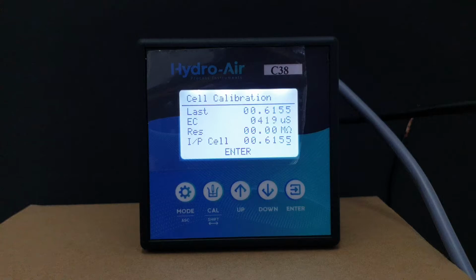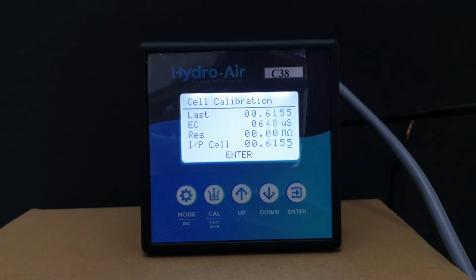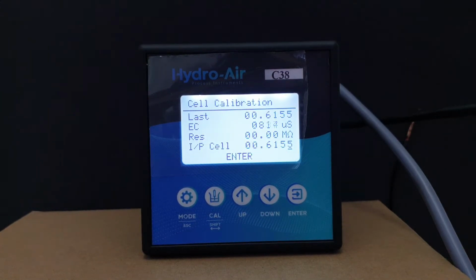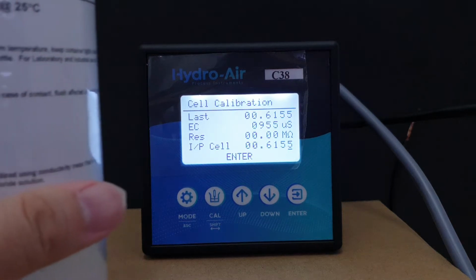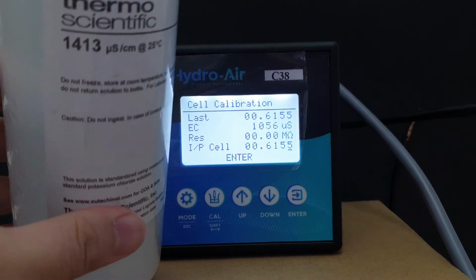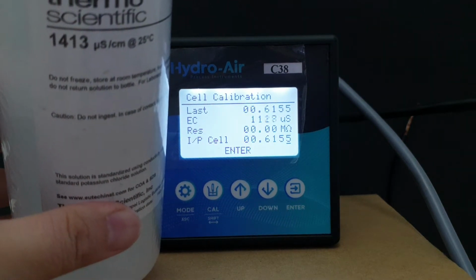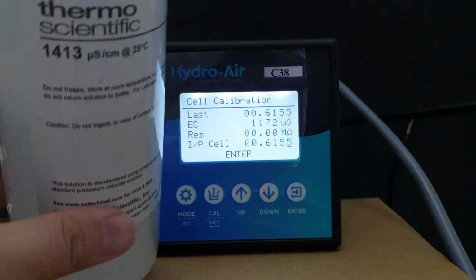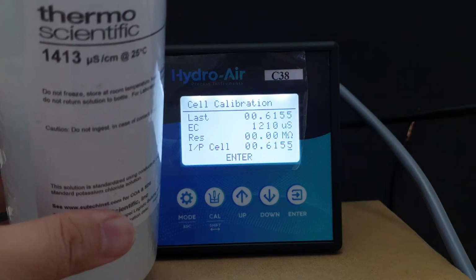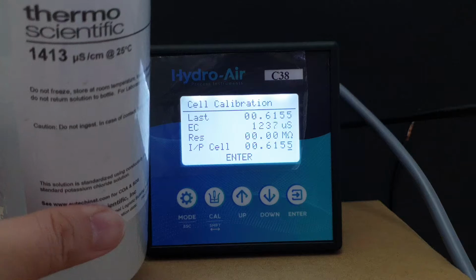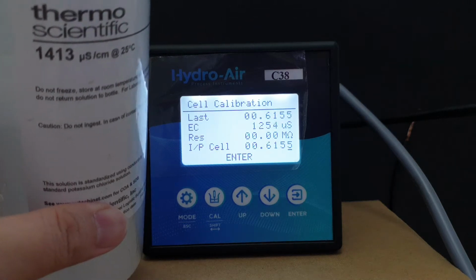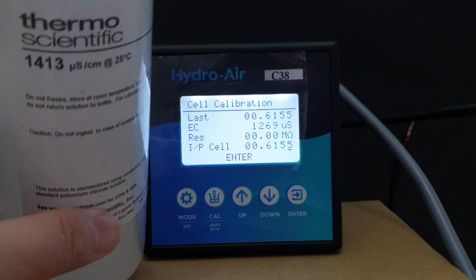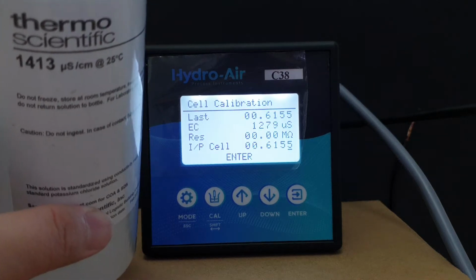Now this is for a better accuracy calibration. So as you can see over here, my buffer is 1413 microsiemens. So later we are going to adjust this IP cell until we get the matching conductivity value.